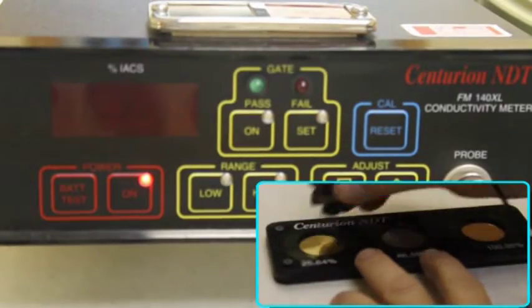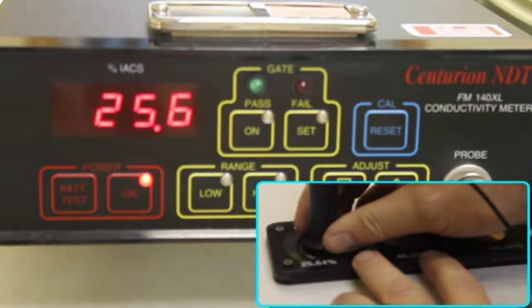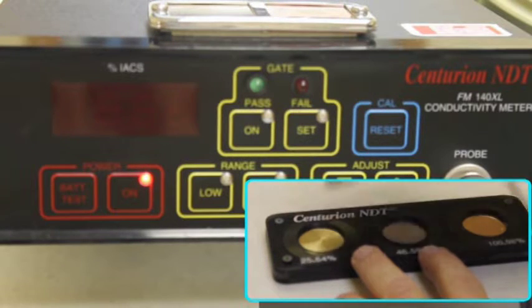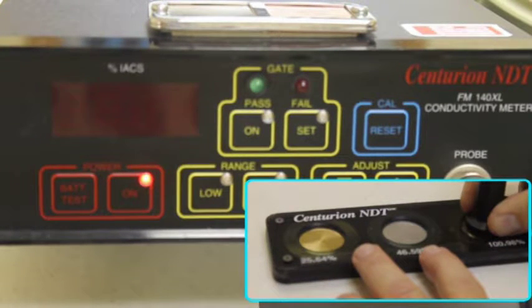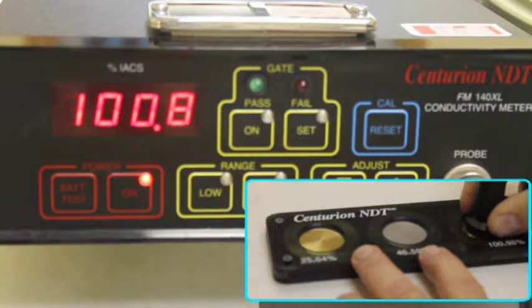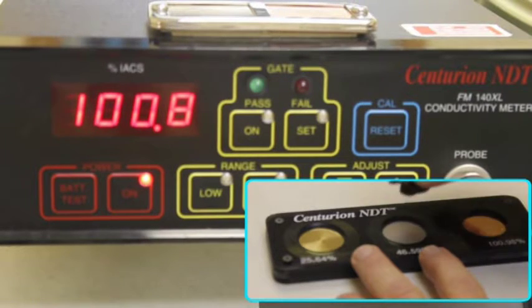Now that the FM-140XL is set up, you can use it to determine conductivity values for your particular application. Many times the specification will specify the expected value. There will always be a tolerance associated with these values, whether it's the raw material or after a heat treatment. Centurion NDT can supply NIST traceable conductivity standards. These are typically housed in a 3-standard set and are required by many aerospace specifications.